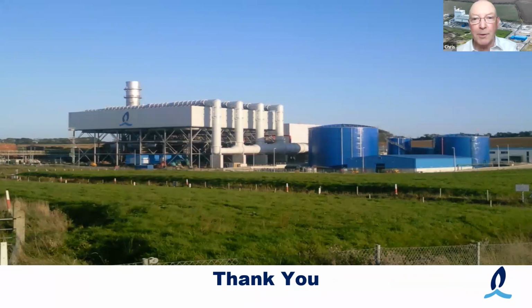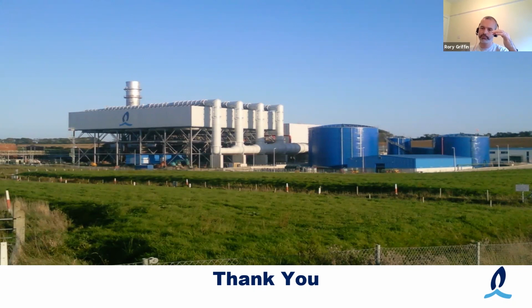Okay. From James Doyle. In the LP boiler, what is the process for removing the oxygen from the water? So that's up at your deaerator, your dissolved oxygen. From memory, the water comes in the top and there's a series of plates. As it hits down through the plates, it releases the gases, oxygen being one of them. And then they get vented out the top.